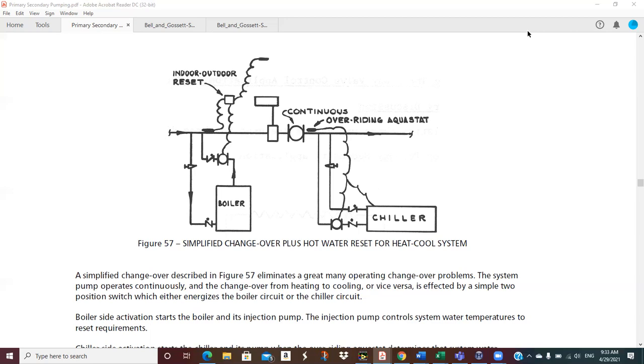And then they have to provide cooling. And they were too cheap to buy a four-pipe system. They didn't want to put two coils in every space so you could circulate them both and then let the controls pick. So you actually do a changeover during the day, from heating to cooling. And then once the sun goes down, it gets cold outside, you go back to heating, and you do that a lot of different days. Excuse me. So you have to be a little careful, because that chiller really doesn't want to see 140-degree boiler water. That's a good way to wreck a chiller. And that boiler doesn't want to see 42-degree chill water. It's going to be a bad day in the plant if you do that.